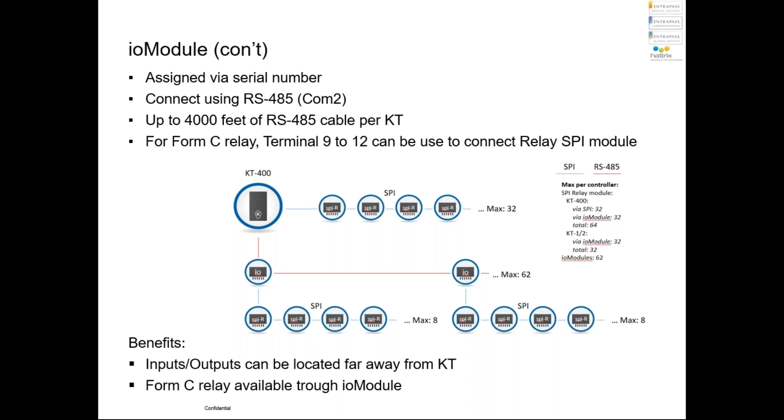And there is one more thing. We have four banks, right? We can use the third bank, which is terminal 9 to 12, as a bridge to connect SPI module. That means we can, for example, have a KT400 controller, connect that IO module with the distance we want from 1 feet to 4,000 feet, and still able to connect SPI relay module to the third bank and keep going with SPI relay module.